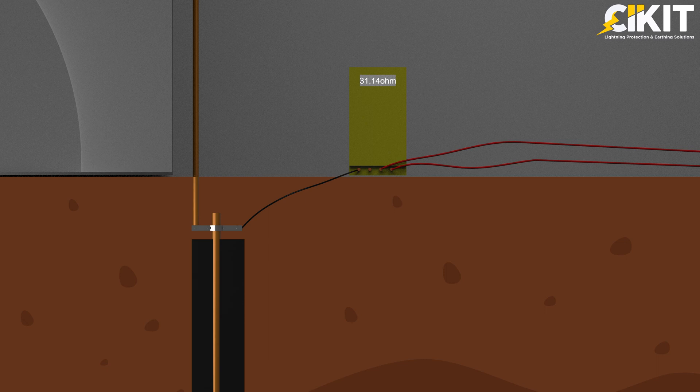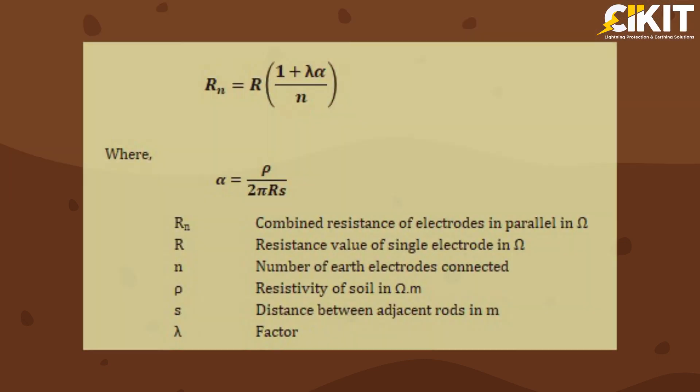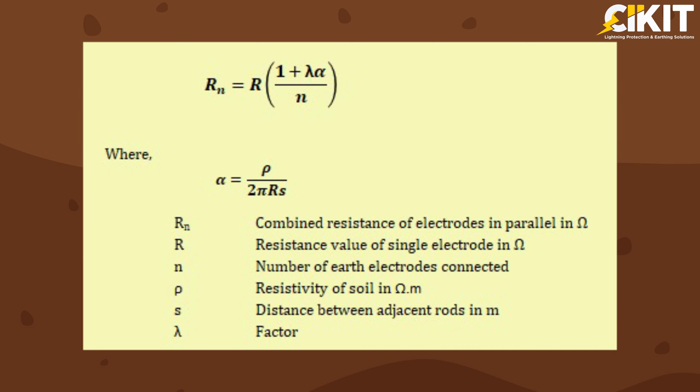If we want to decrease the resistance further, we have to add multiple earth electrodes in parallel. To calculate combined earth electrode resistance, IS-3043 has given the formula.